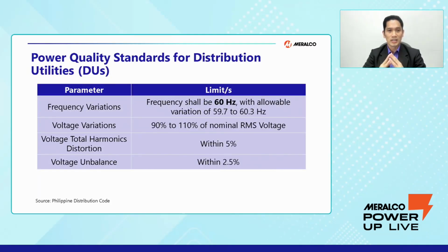As stated in our Philippine Distribution Code, these are some of the standards for the distribution utilities. First is the frequency variation. Our frequency in the Philippines is 60 Hertz, with an allowable variation between 59.7 and 60.3 Hertz. Although Meralco does not directly control the frequency, as it is the function of our system operator, the NGCP, we assist in maintaining the frequency within this range. Thus, we do manual or automatic load dropping to maintain the balance between supply and demand.